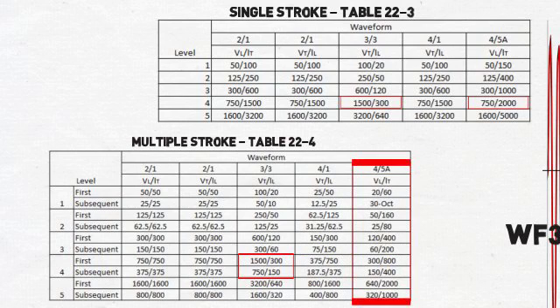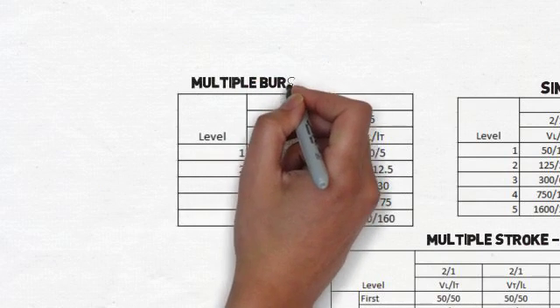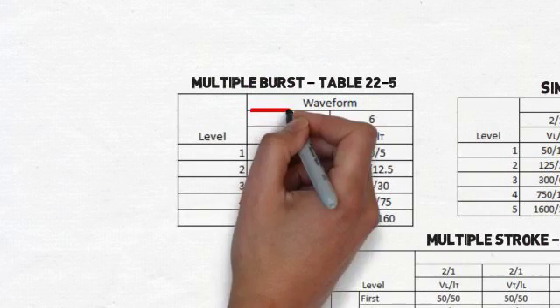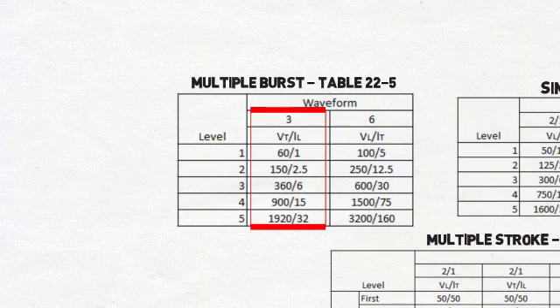Likewise, waveform 5A is tested at 300 volts and 800 amps for the first stroke, while subsequent strokes are tested at 150 volts and 400 amps. And last, category L3 for multiple burst specifies that we will test waveform 3 to level 3.